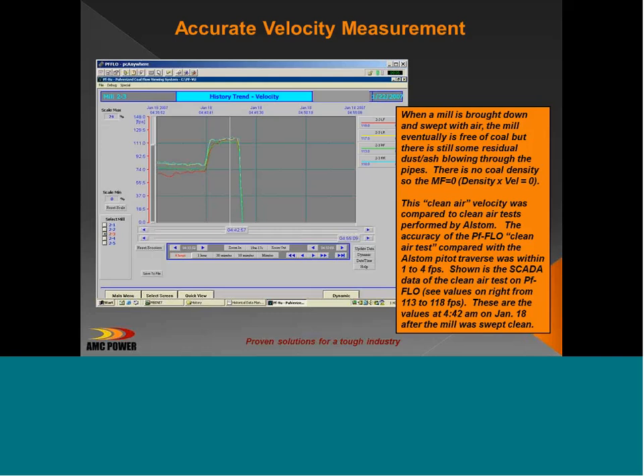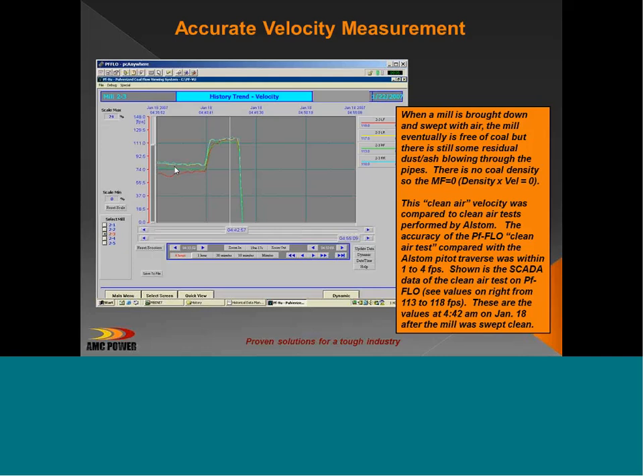So now we're still measuring velocity because there's still movement in the pipe, but now what we're cross-correlating is the dust that remains from the air preheater. And this is an important screen because what it depicts is that without a change in primary air, tracking the fuel velocity, we see a much lower velocity, 60 to 80 feet per second. But the air velocity in a coal pipe is much higher. The difference between these two is the slip.